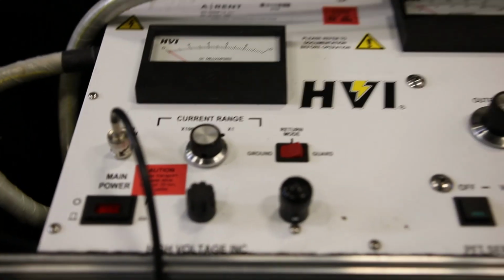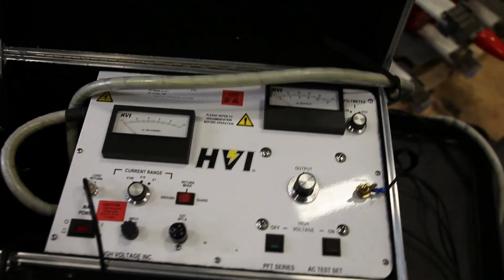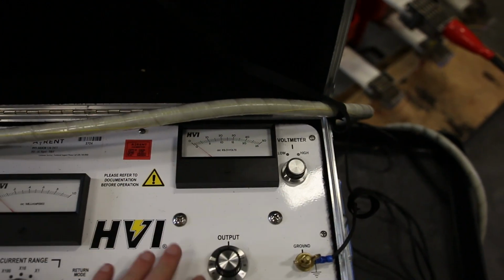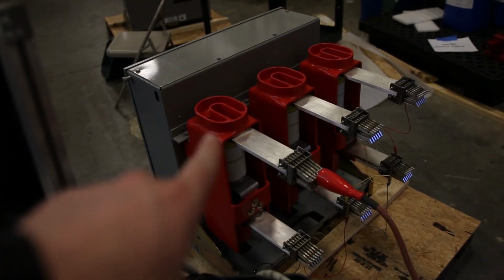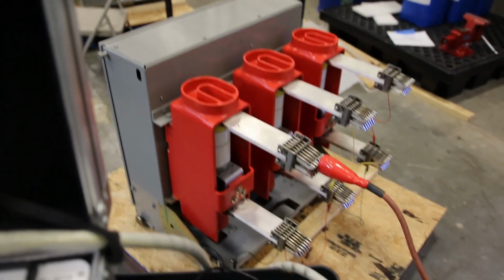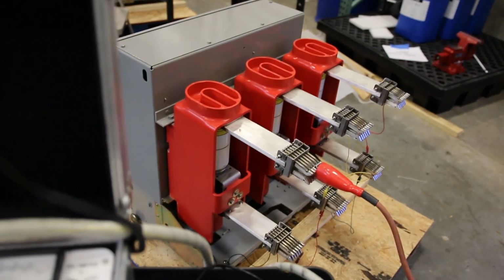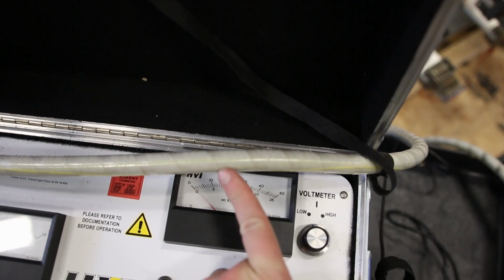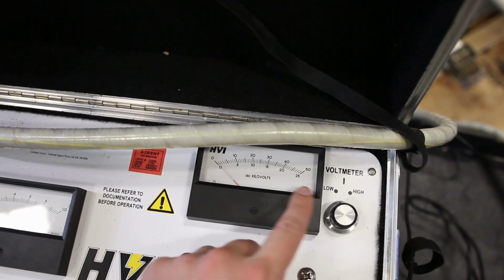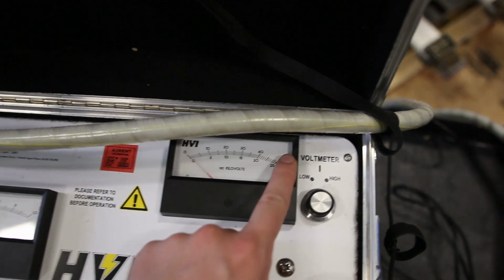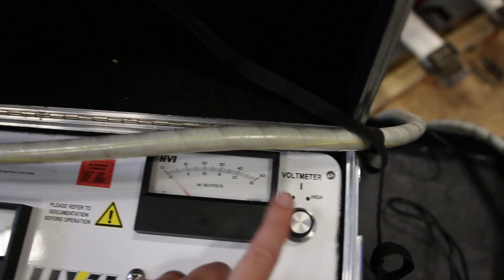All right, zoom out. So the controls on this guy, per my manual, this is a 4160 volt breaker. It's a VR, I can give you the part number, it doesn't really matter. According to the manual, we're going to high pot at 14 kV AC. So our range selector knob needs to be in the low position, which means we're going to the bottom scale on here, which maxes out at 25. We don't want the one that goes to 50, we want the one that goes to 25, so we're on low.